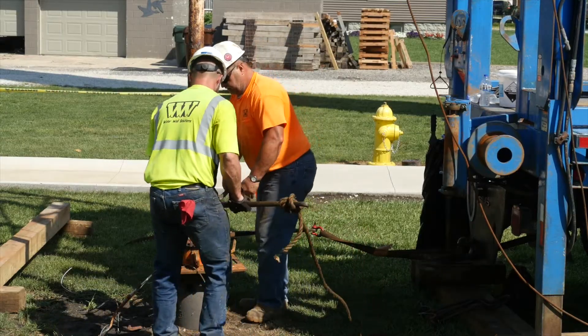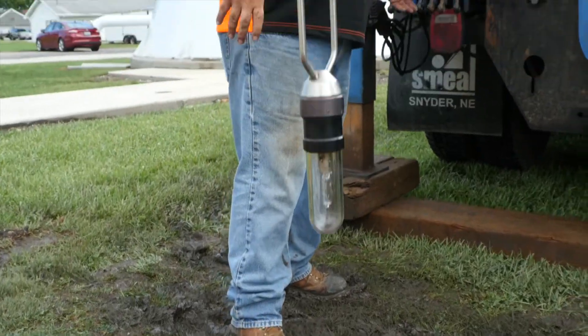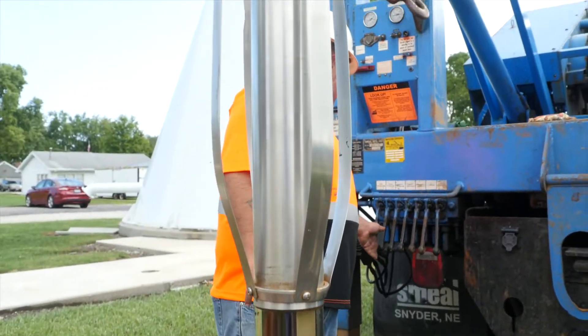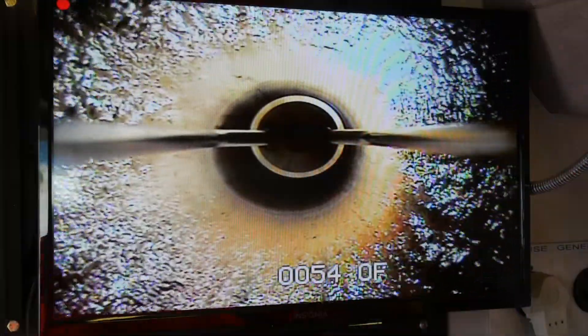They pulled the well and the pump. They did a video taping and discovered that there was a lot of tuberculation on the well casing. They identified the source — the pitless adapter was leaking, bringing in water from outside, causing the corrosion and tuberculation. With that tuberculation, that harbors bacteria.